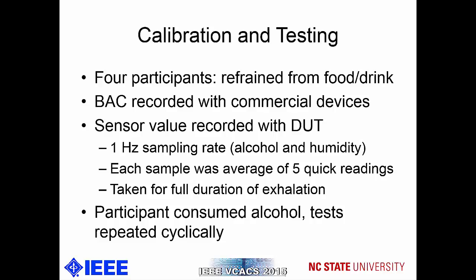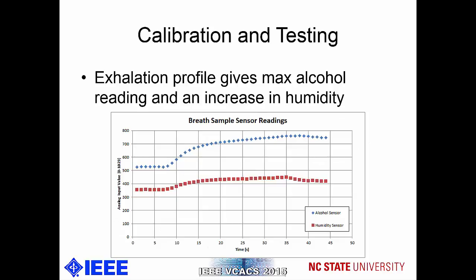One breath analysis with our device was based on about a 1-minute sample of alcohol and humidity readings, each taken at a frequency of 1 Hz. Each reading was low-pass filtered by averaging 5 ADC conversions. This test was repeated until enough data points were captured. Here's an example exhalation profile of alcohol sensor readings and humidity readings.